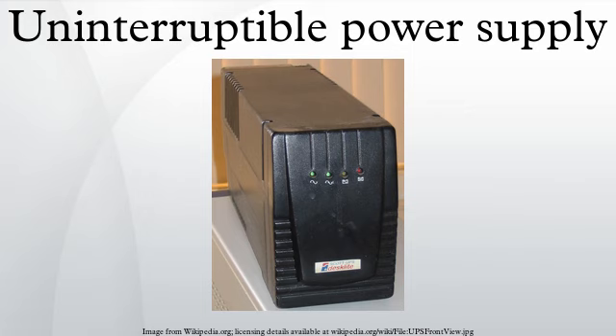The newest technology in double conversion UPS units is a rectifier that doesn't use classic rectifier components but high-frequency components. A double conversion UPS with an IGBT rectifier and inductor can have a THD-I as small as 2%. This completely eliminates the need to oversize the generator, without additional filters, investment cost, losses, or space.